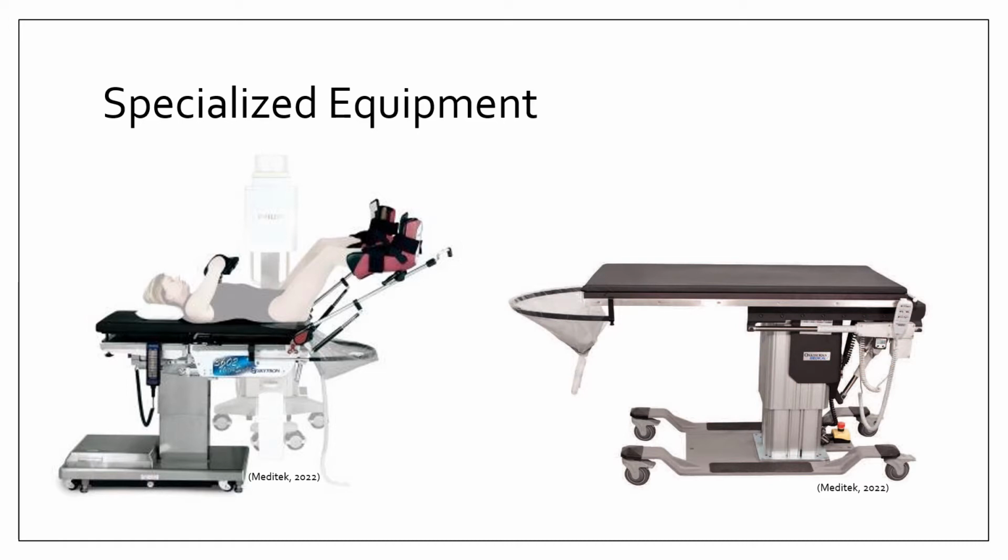We also do have a portable cysto table. So similar to that bed on the right, it has the same kind of function. You have to add the stirrups that the patient's legs will go into, but it can move from room to room. So if there are multiple cystoscopy procedures being done, or for whatever reason room 9 is out of service, we can perform these procedures in other rooms.